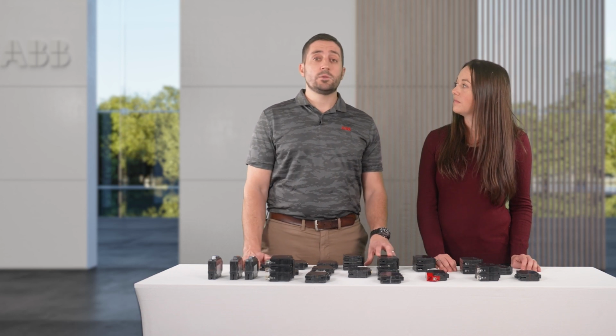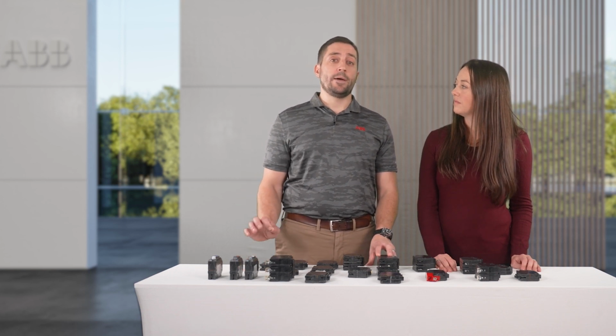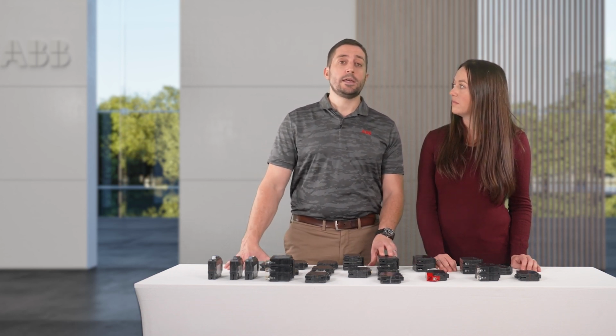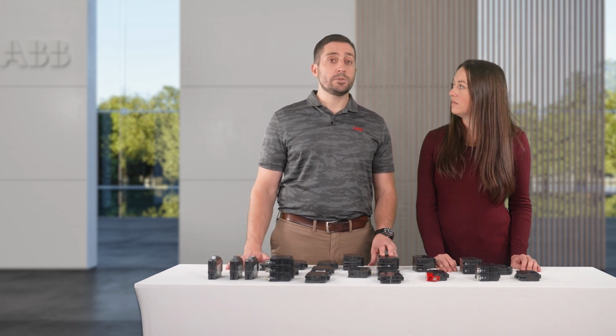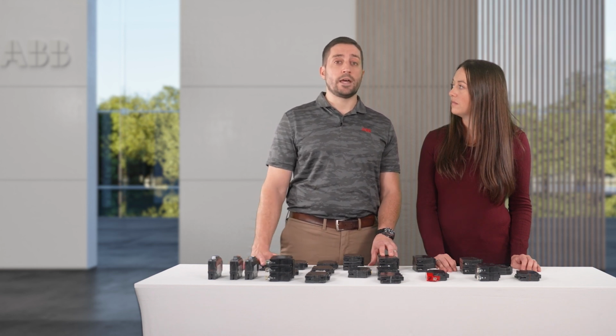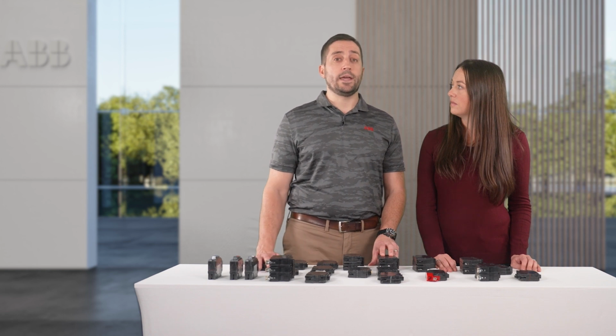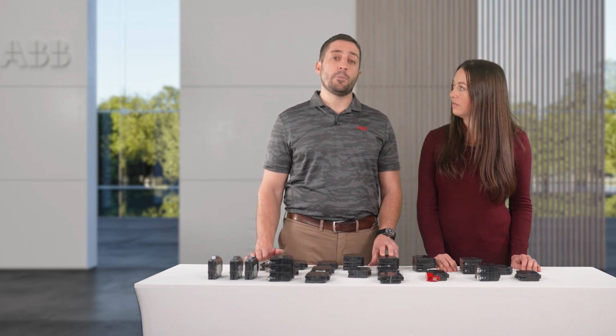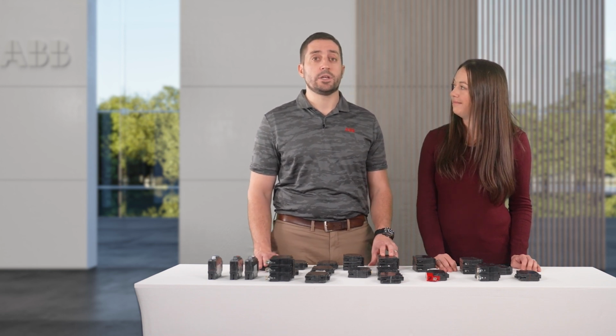As technology is continually changing, we are required to adapt the electronic miniature circuit breakers. If an electronic miniature circuit breaker trips, we recommend, when going on site, resetting the breaker and reviewing the LEDs located on the ground fault, combination arc fault, and dual function breakers to begin troubleshooting.